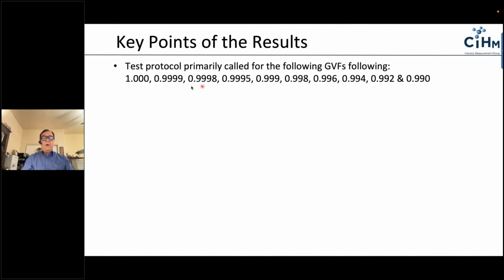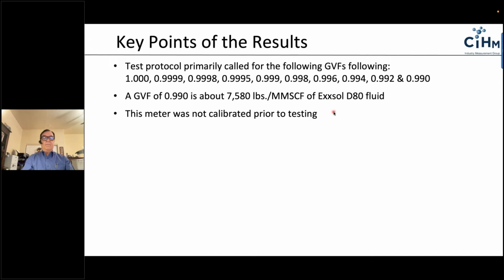So the primary protocol was to look at some minor light liquid loading. So we started off with 100% gas volume fraction and worked down to the 0.99, which is the 1%, but we can see some very small light liquid loading. They wanted to see what the performance would be and what the diagnostics would say. So here's only a 0.1% liquid loading at this point. So we had some very, very small liquid loadings, and then we started jumping in 0.1 and 0.2% increments all the way down to the 1% by volume liquid. The gas volume fraction of 0.99 equates to about 7,500 pounds per million standard cubic feet of Exxsol D80. Obviously not pipeline quality gas. This meter was not calibrated prior to testing.